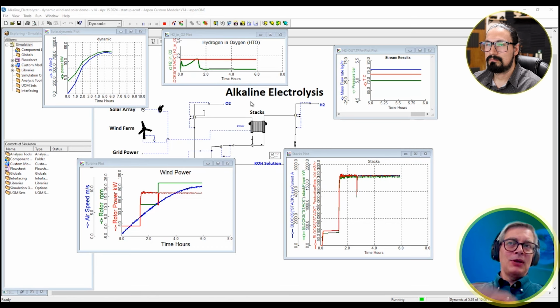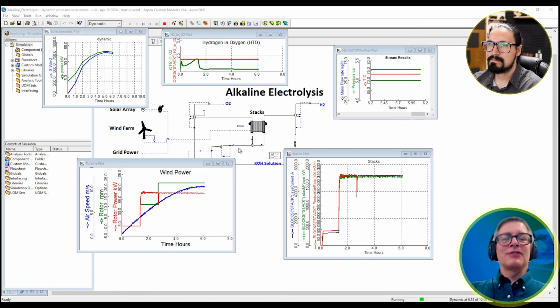For example, it might be pump failures. If I lose this circulation pump, I'd have to shut down, and then there's some period of time required to fix that pump. I could improve that performance by having two pumps in parallel, so I have a standby, or three pumps in parallel, each able to handle 50% of the capacity. There are many different scenarios that would influence the capital cost and the expected uptime.